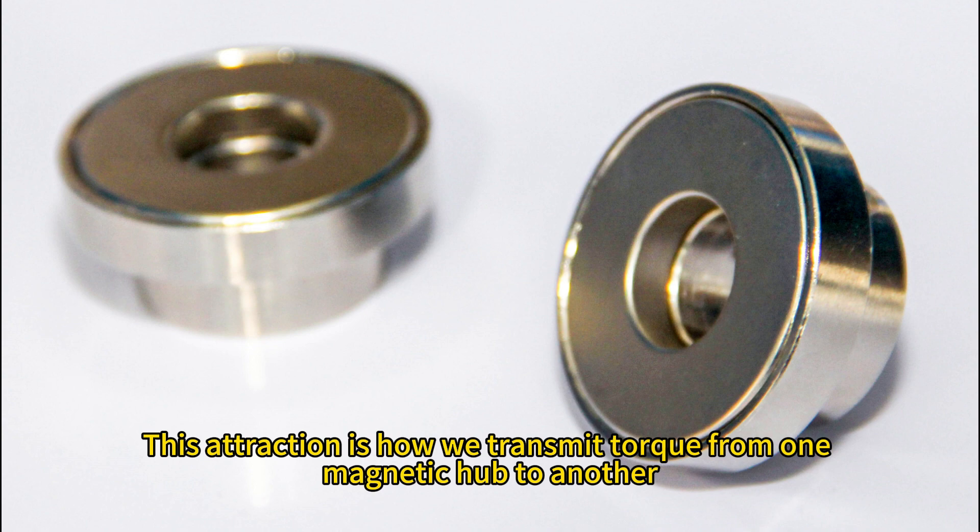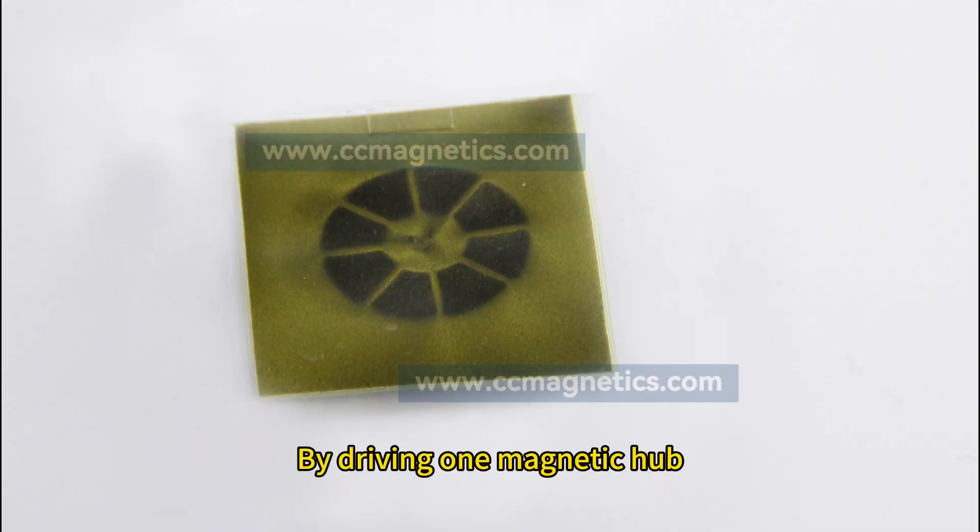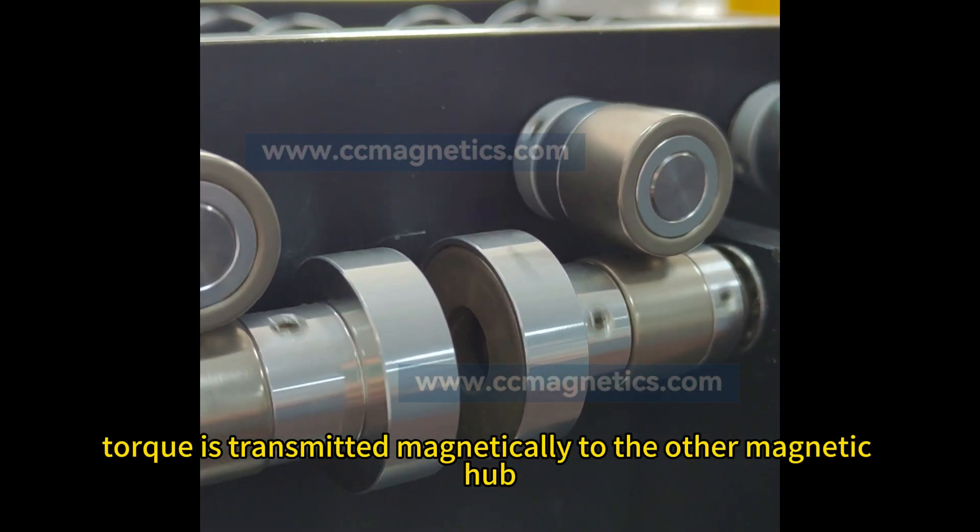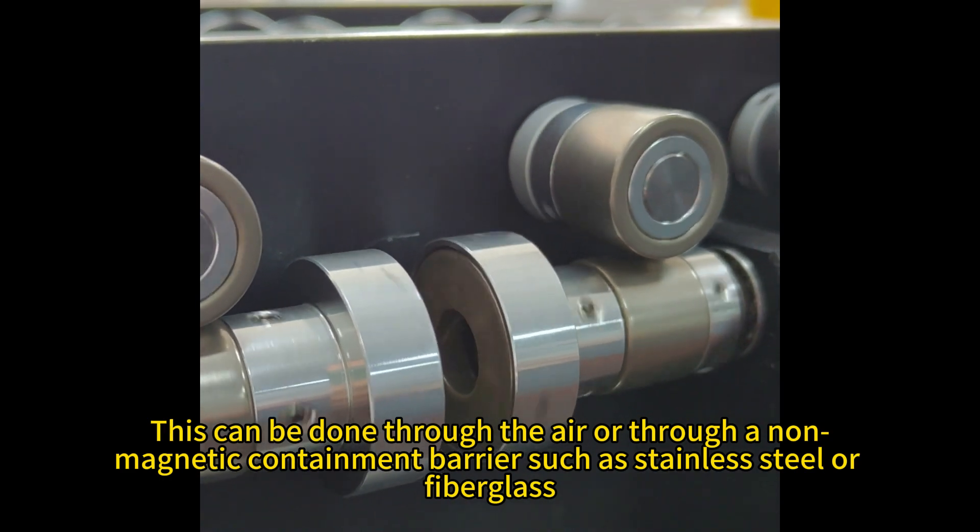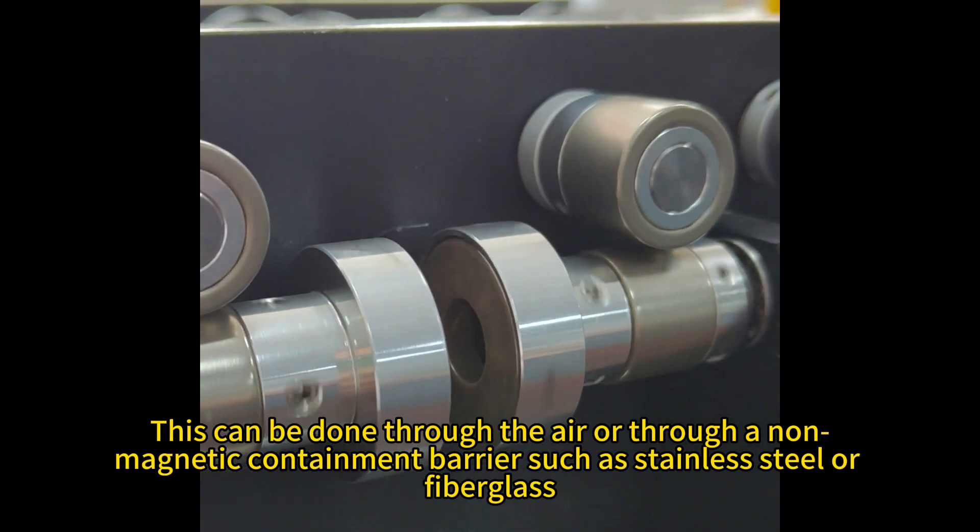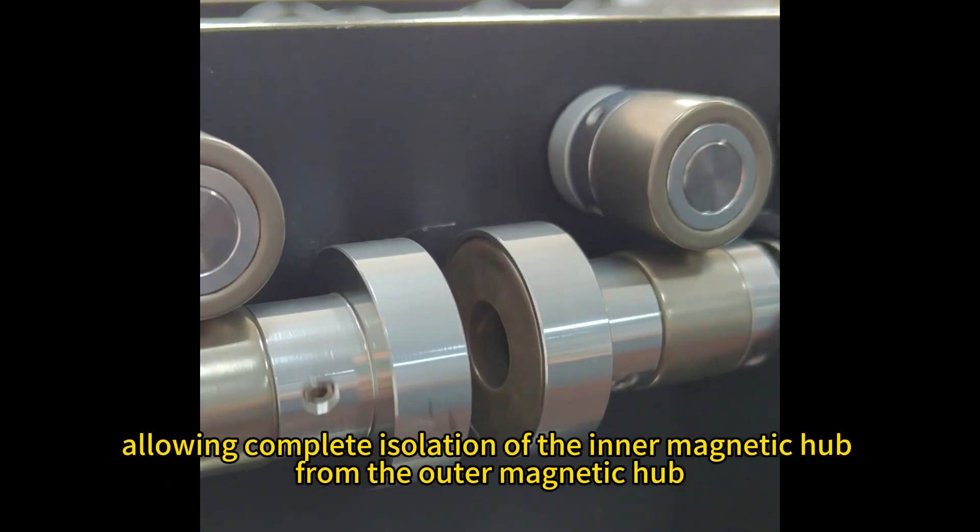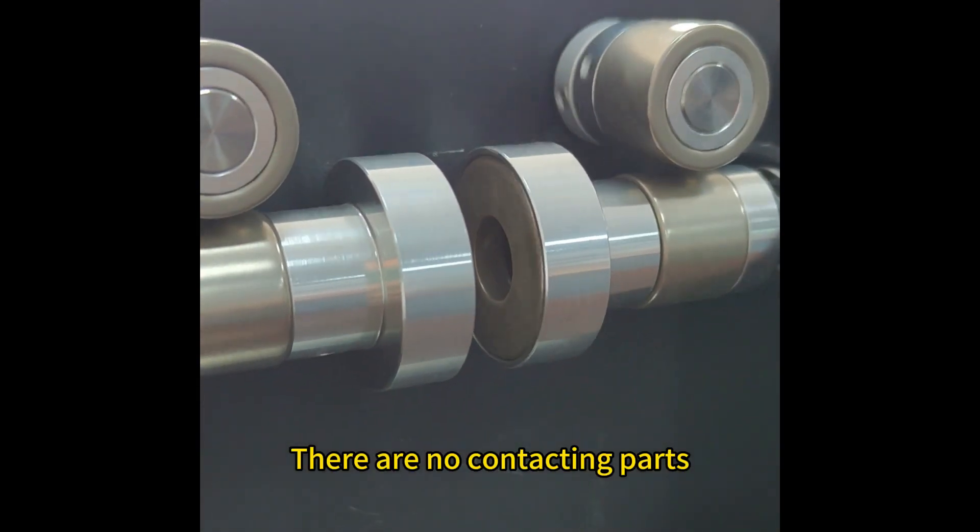This attraction is how we transmit torque from one magnetic hub to another. By driving one magnetic hub, torque is transmitted magnetically to the other magnetic hub. This can be done through the air or through a non-magnetic containment barrier such as stainless steel or fiberglass, allowing complete isolation of the inner magnetic hub from the outer magnetic hub. There are no contacting parts.